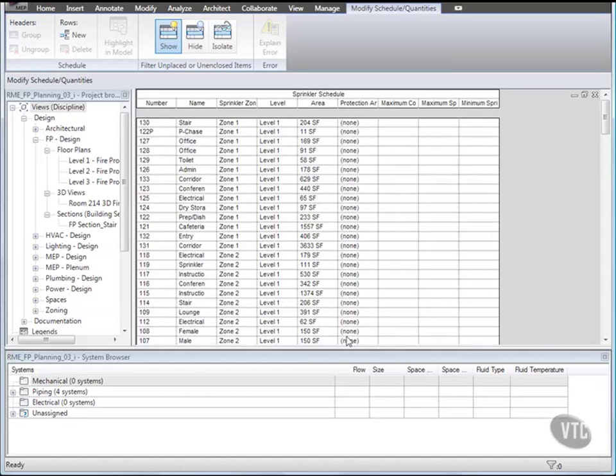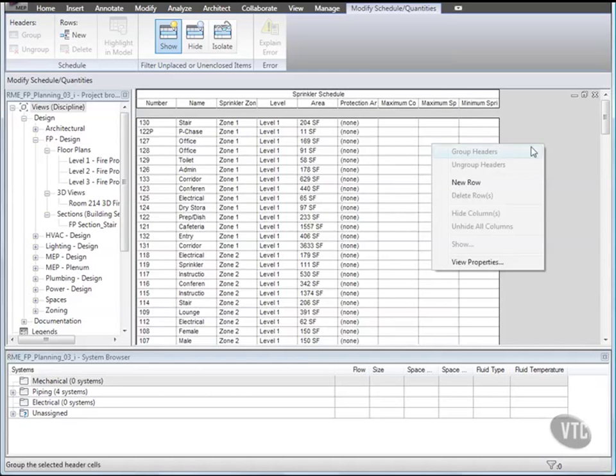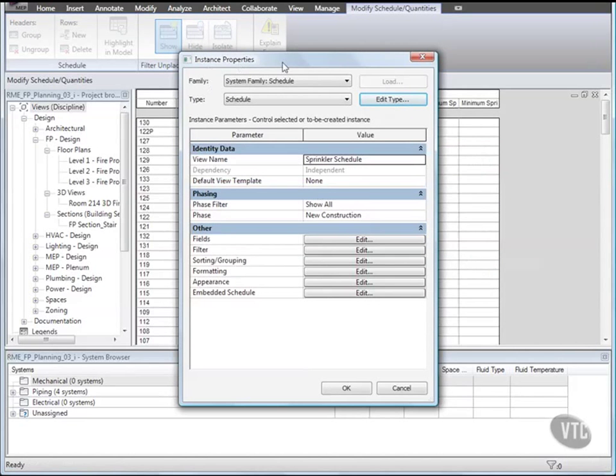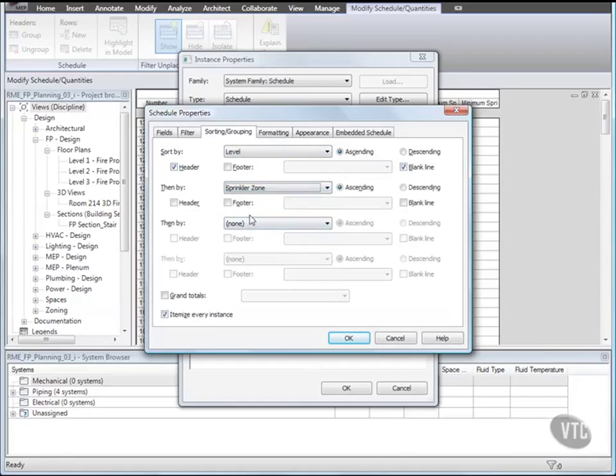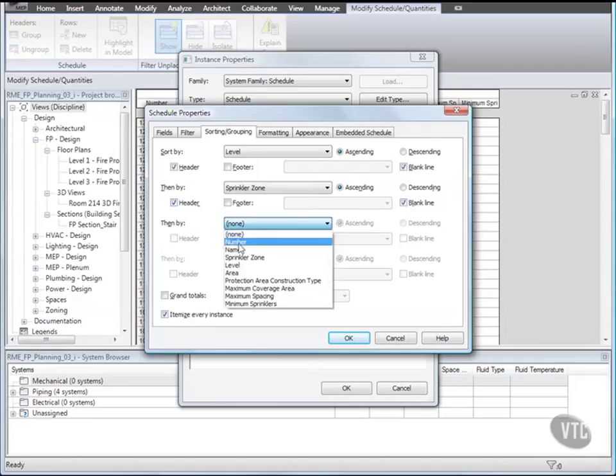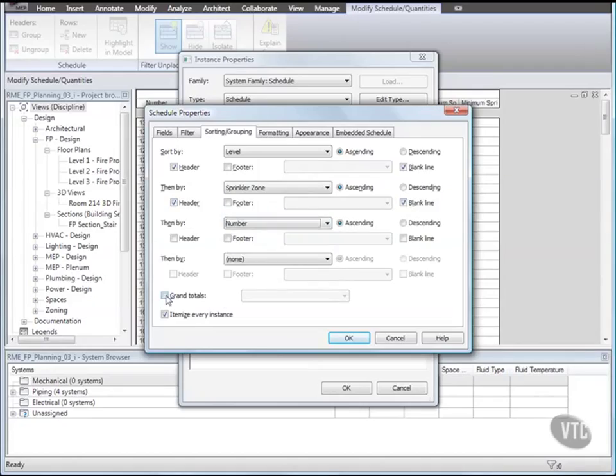Next we'll organize the schedule data. Right-click in the schedule and click View Properties. Then in the Instance Properties dialog, under Other, for Sorting and Grouping click Edit. On the Sorting and Grouping tab, for Sort By select Level. Then click Header and Blank Line. For Then By select Sprinkler Zone. And then click Header and Blank Line again. And for the second instance of Then By select Number. And at the bottom of the dialog select Grand Totals, and then select Totals Only.